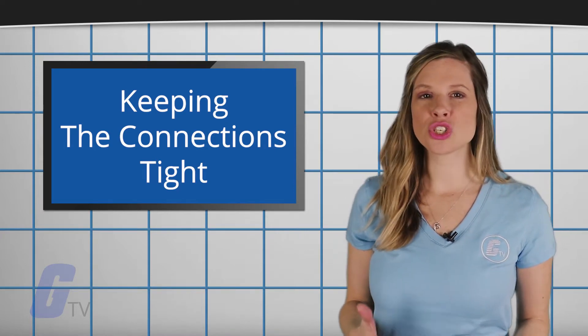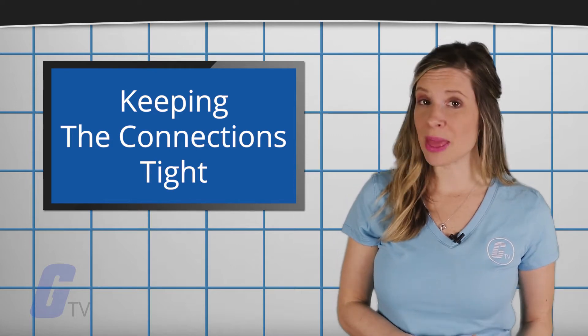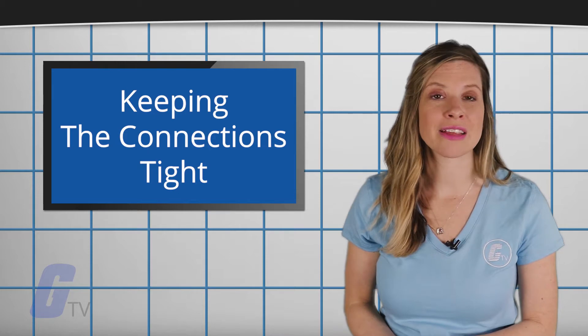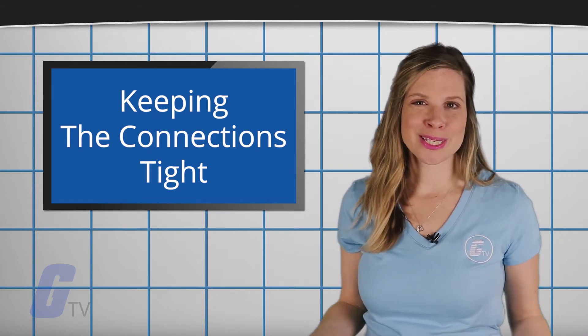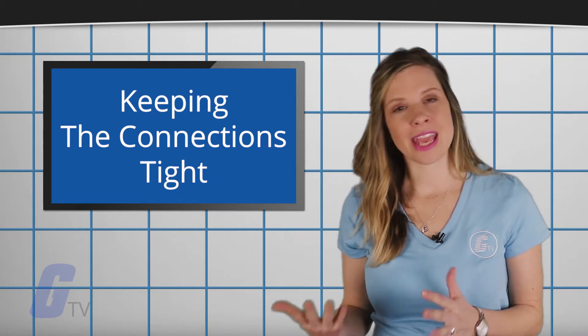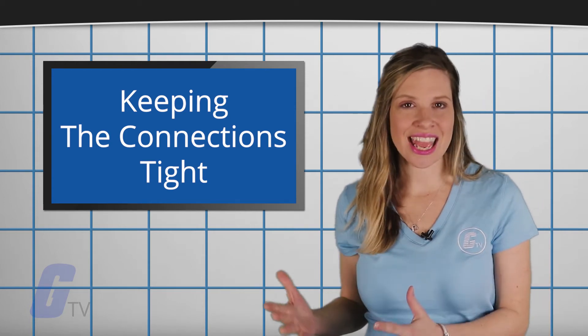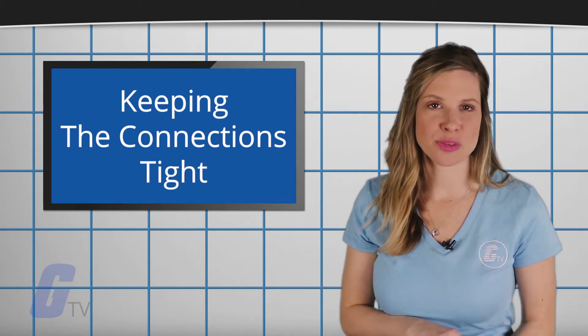As simple as it sounds, checking your connections is a step that many people can miss or do incorrectly while doing their preventative maintenance. Over the course of time, heat cycles and mechanical vibrations can cause substandard connections, as can incorrect preventative maintenance practices.